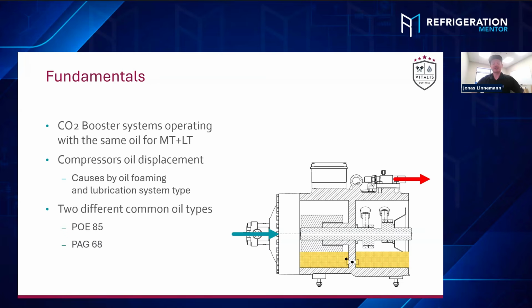And why do we actually have oil in that system? In CO2 systems, we typically have the reciprocating compressors, as you can see here, a little simplified cut model. And these compressors basically just need oil for lubrication. That's very important. Every compressor works a little different. So here you can see these oil circulation discs. Other compressors also come with oil pumps, so forced lubrication. So there are slight differences, but at the end of the day, they all do the same thing.